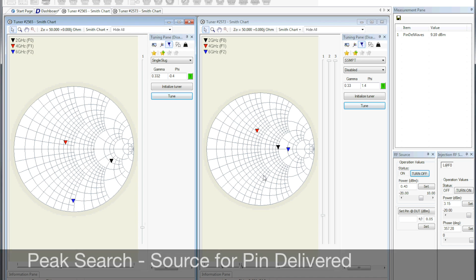As the first step, we will perform a peak search on the source of the device to determine the optimum impedance for delivered power. The software's algorithm varies the input impedance until it finds the optimum point for the measured parameter at a fixed power level. We then perform the same algorithm on the output, but this time for gain or output power. This will help us determine our match at small signal and serve as a starting point before we move on to large signal measurements.